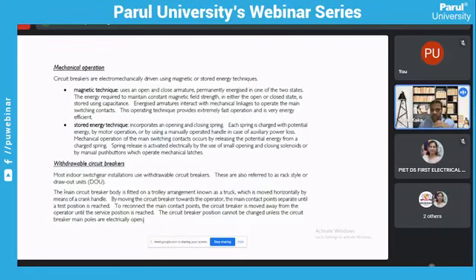Now, this is just a basic technology. What is actually driving the circuit breaker? Breakers are just electromechanically driven using magnetic as well as stored energy techniques. Normally, vacuum circuit breakers have closing as well as opening springs. Each spring is charged with potential energy. It is held with that particular charge by a motor operation, and by using a manually operated handle you can also charge the spring in case we lose any auxiliary power.